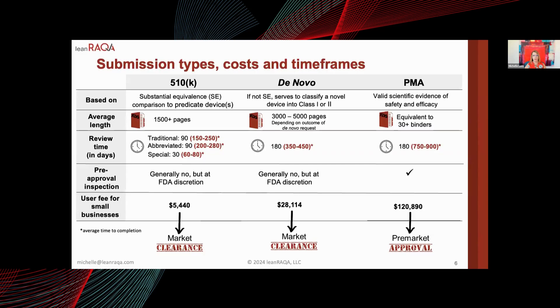Generally, 510ks and de novos don't require an inspection before you can market your products, whereas PMAs require a pre-approval inspection. By comparison, anything besides self-certified products in the EU requires a notified body review for both your quality management system and your submission technical file content.